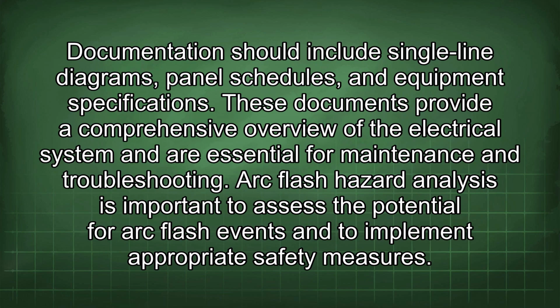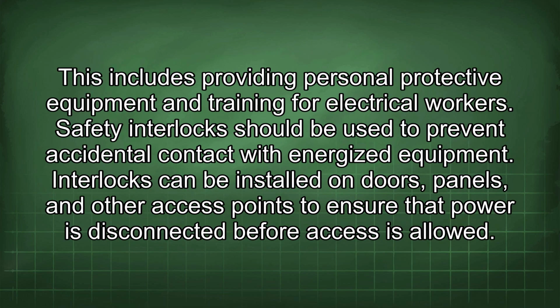Documentation should include single-line diagrams, panel schedules, and equipment specifications. These documents provide a comprehensive overview of the electrical system and are essential for maintenance and troubleshooting. Arc flash hazard analysis is important to assess the potential for arc flash events and to implement appropriate safety measures. This includes providing personal protective equipment and training for electrical workers. Safety interlocks should be used to prevent accidental contact with energized equipment.